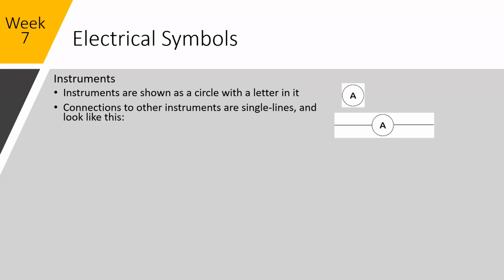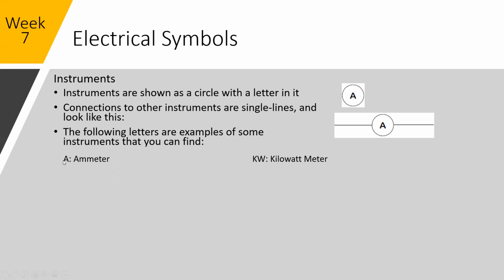P&ID electrical symbols, that's correct. We can get to those. There are lots of other letters that you'll come to, and the important thing to realize is that although there are some standards out there, P&ID, there are some IEC and I can't think of the acronym for the Automation Society. ISA has some standards for P&ID drawings. It's important to know that these symbols might change based on the country that you're in, based on even the company that's supplying them. And you always have to look for the drawings that you have.